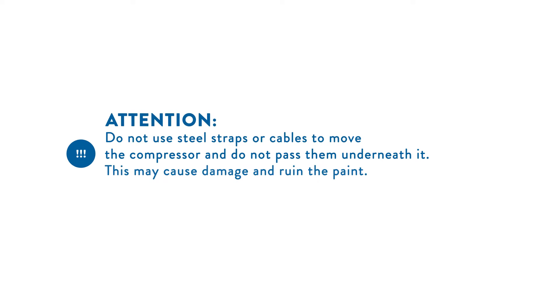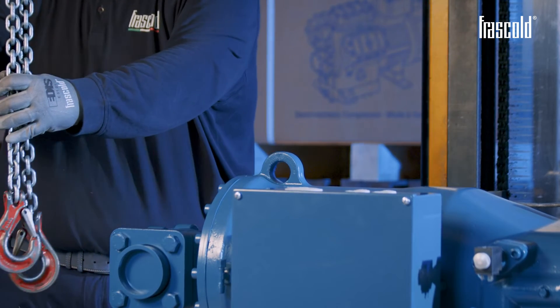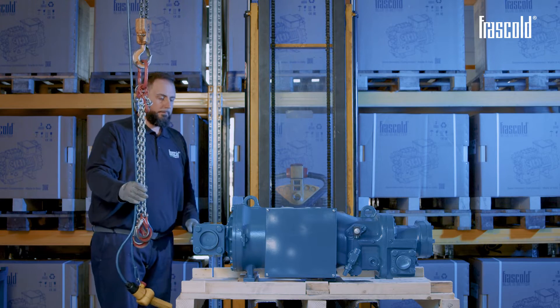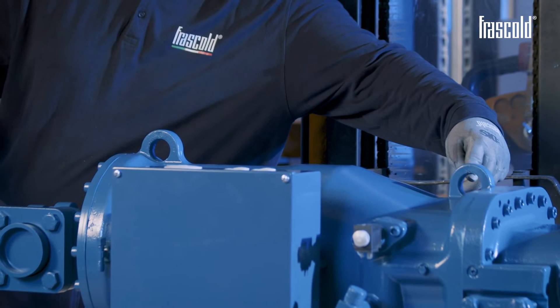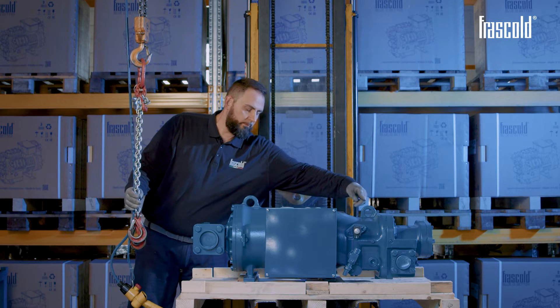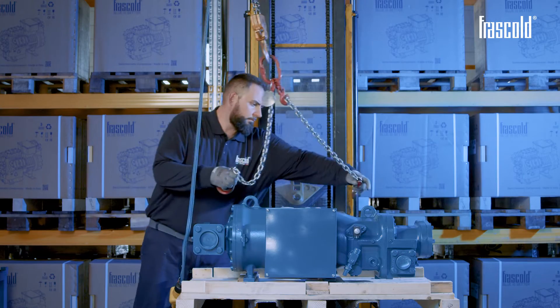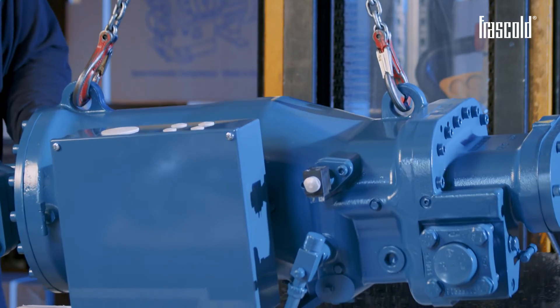Attention: do not use steel straps or cables to move the compressor and do not pass them underneath it. This may cause damage and ruin the paint. To move the compressor, it is necessary to use a crane equipped with suitable lifting and handling equipment. If a crane is not available, use a forklift or a suitable lifting tool. For handling operations, use the anchor points on the compressor. Make sure that the compressor does not hit the valves, electrical components, or piping, as this could cause damage.